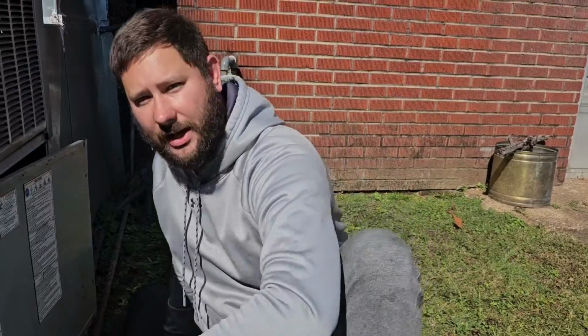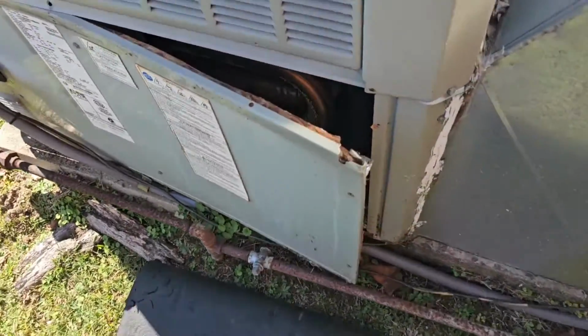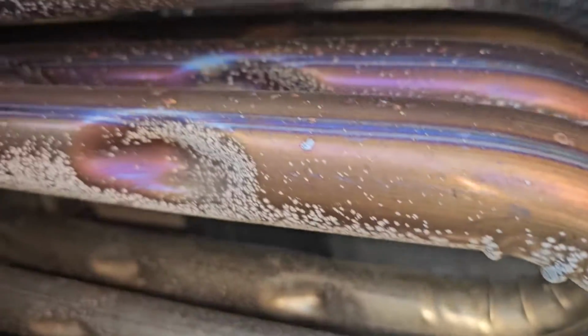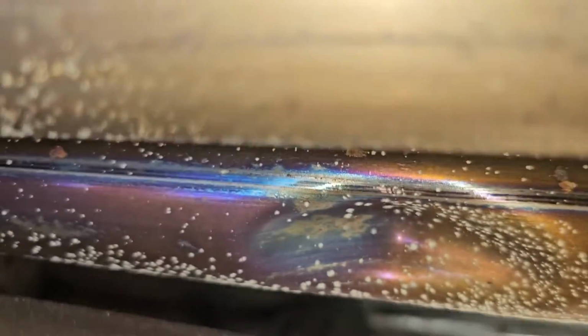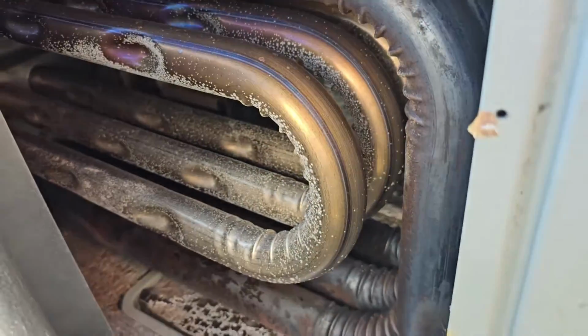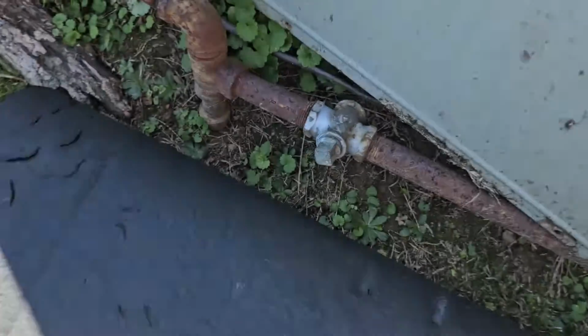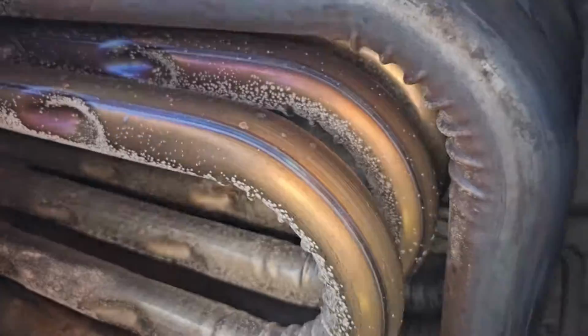I'll show you this heat exchanger here. It looks really good, this is a packaged gas unit. I'm going to turn the light on. You can see we've got no cracks. This heat exchanger is fairly new, but you need to make sure that you shut that gas off so that the customer cannot turn it back on.